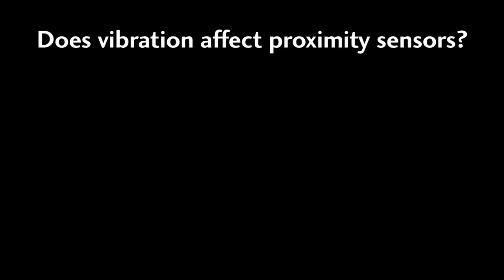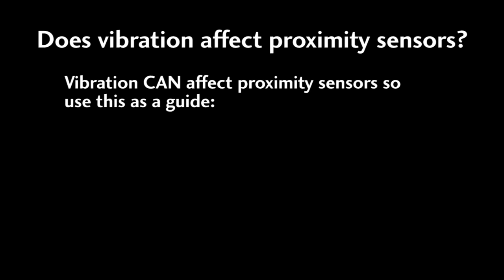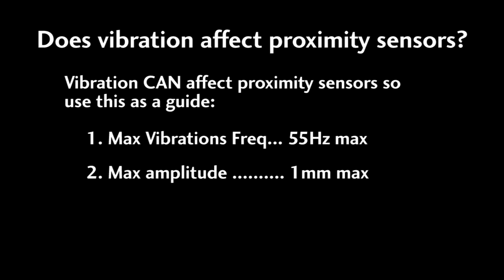Can you use a proximity sensor in a vibrating environment? You can, but keep the vibrations below 55 Hz and a max amplitude of 1 mm for no longer than 30 minutes on any axis.